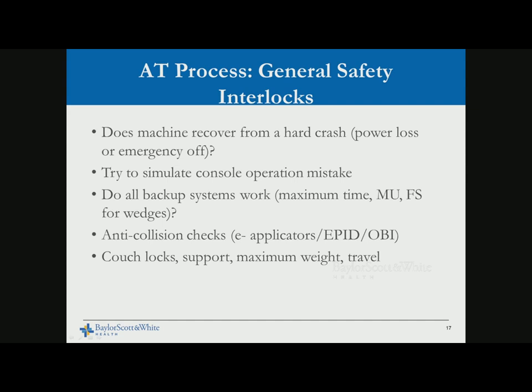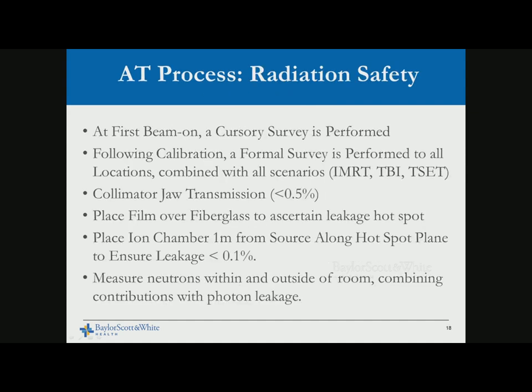The first and foremost important thing is general safety. Even before doing radiation safety testing, you need to make sure the machine has the right safety features for the installer, staff, and the machine itself. This includes testing all anti-collision checks, couch locks, maximum weight-bearing level, and whether the emergency switch and connections are working — this is very important even before starting the radiation test.